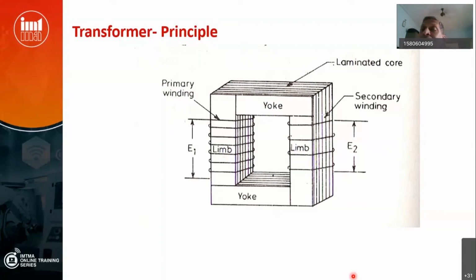On the 415 side, in the transformer, one is the receiving end, one is the sending end. The receiving end is primary, this is primary, this is the secondary. Primary is always in delta, because in a three-phase transformer, 3 windings are there, so they have to be connected either in star or delta. Generally, the primary side is connected in delta, and the secondary side, the sending end, from here the transmission line starts. Here, this particular side is connected in star.